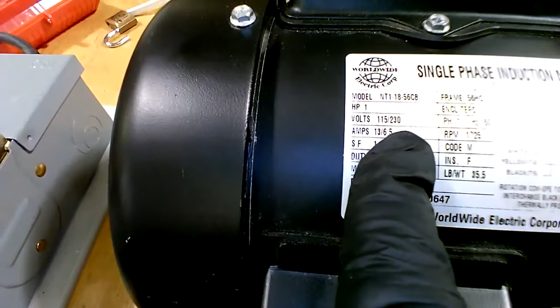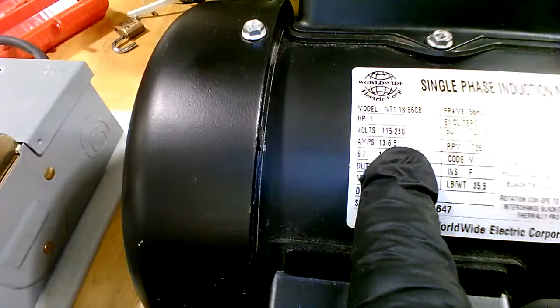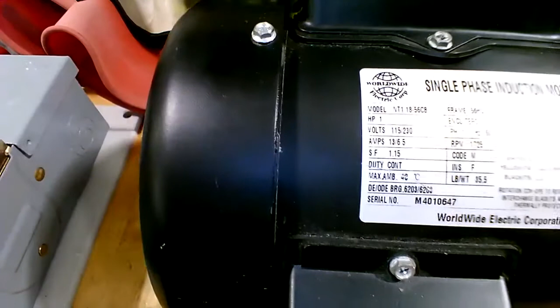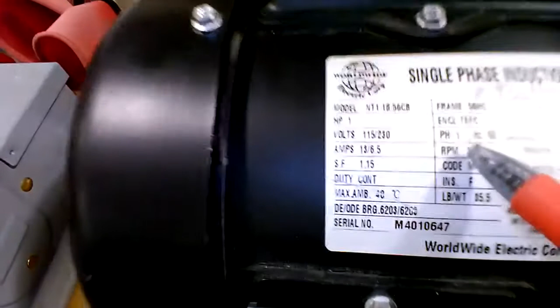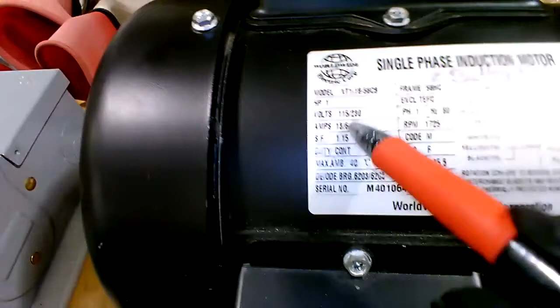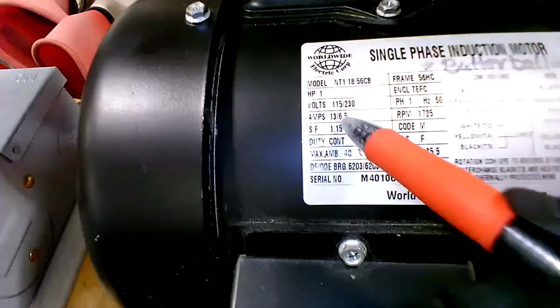So let's go to the nameplate. The nameplate shows the running amps should be 6.5 amps at 230. Now, there was actually no load on it. What did you draw? It was 4.5 amps. Right. So he's drawing less than what it says here. You've got the 115, 230, and at 230 volt, 6.5 amps. We're running at 208 volt, and you actually have even fewer amps here simply because there's no load on the motor. The motor doesn't have anything tied to the shaft. There's no pump or fan tied to it. So it's drawing less than the nameplate. So that's fine.